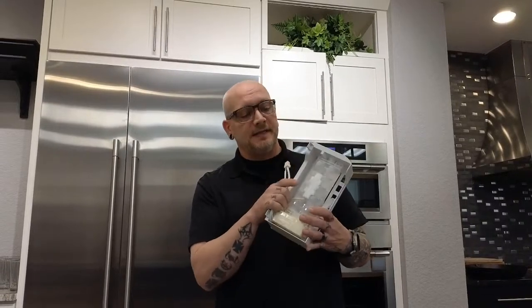So 8 no water in is an error code that the machine will receive if it has attempted to fill with water 10 times and has not changed temperature on the temperature sensor. So here's one of our ice makers. On the bottom of the ice maker, you have an NTC probe. If this probe does not change in temperature when the ice maker fills with water after 10 attempts, it is going to error out 8 no water in. That doesn't necessarily mean we don't have water to the machine. It could be a bad sensor, and the sensor's not reading that it did fill with water or change in temperature, but that's the only reason that we're going to get 8 no water in.